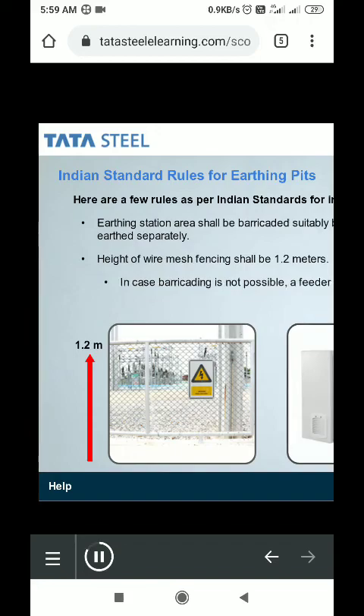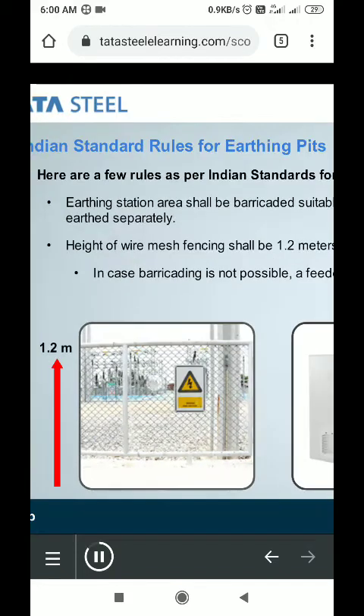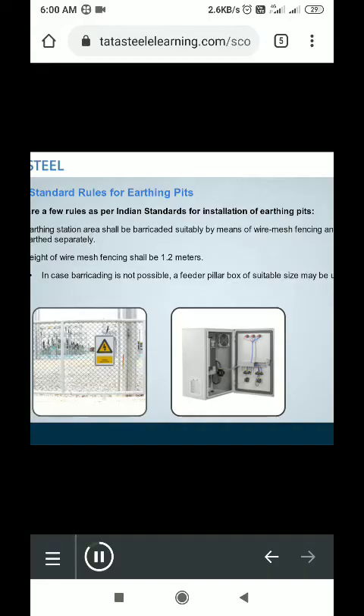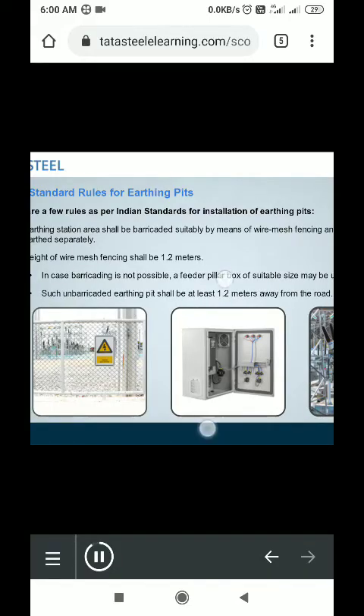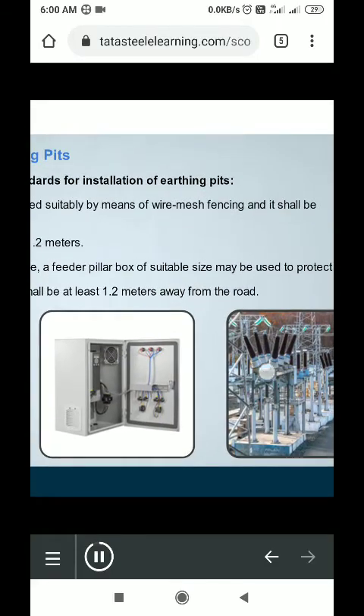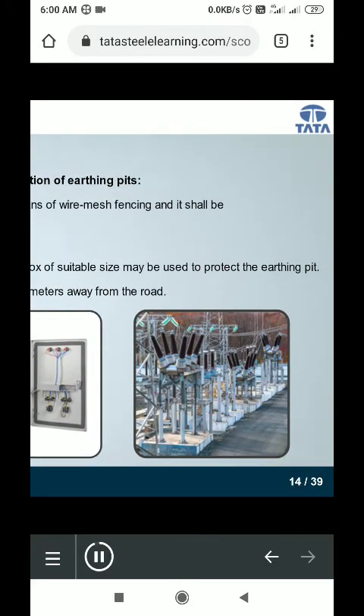If this is not possible, a feeder pillar box of suitable size may be used to protect the earthing pit. Such an unbarricaded earthing pit shall be at least 1.2 meters away from the road. So these are the rules for installing earthing pits.